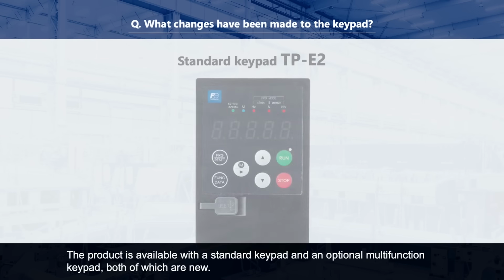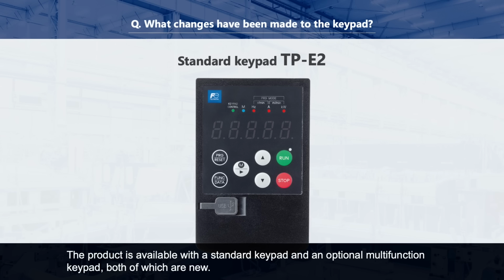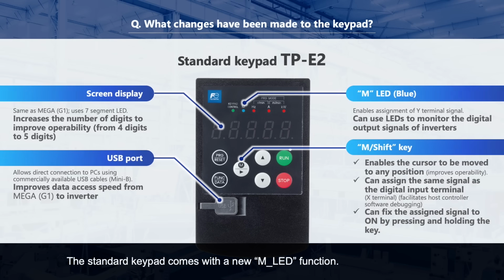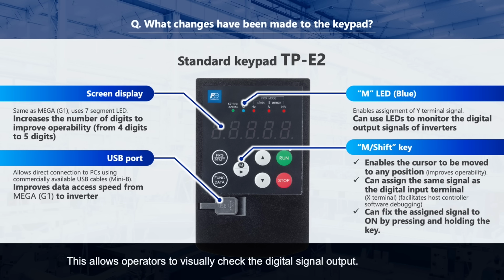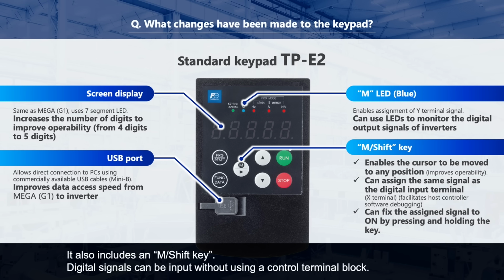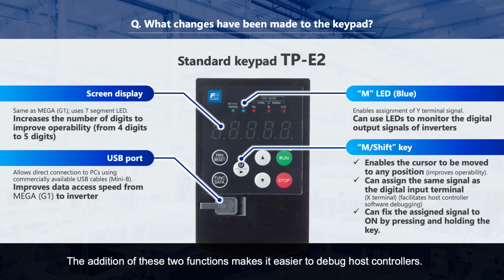Next, let's look at the inverter unit's keypad. It has also been redesigned. The product is available with a standard keypad and an optional multifunction keypad, both of which are new. The standard keypad comes with a new M-LED function. This allows operators to visually check the digital signal output. It also includes an M-Shift key. Digital signals can be input without using a control terminal block. The addition of these two functions makes it easier to debug host controllers.